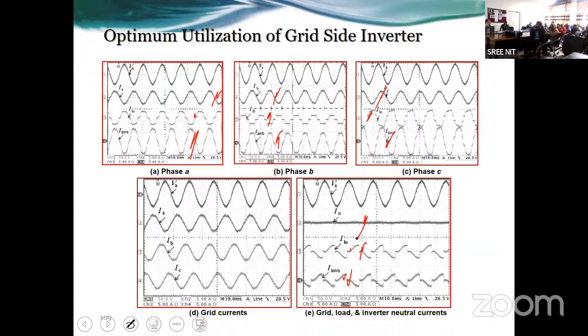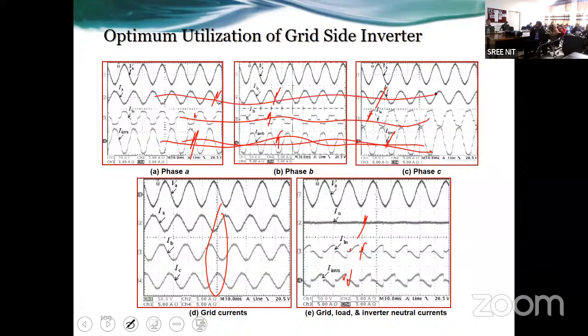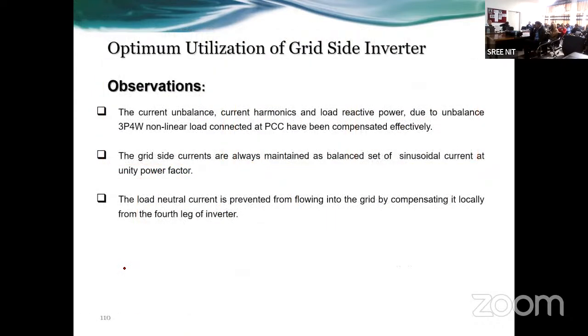So grid side neutral current is 0 because the unbalanced part I am supplying from the inverter itself. So the load unbalanced part I am supplying from the inverter. So that's why these are the perfectly balanced currents. These are the unbalanced part which I am supplying. This is the unbalanced load, unbalanced inverter injection, but these are the balanced grid side currents. Are you getting it? And this is evident from here. Inverter is giving just a complement of the load. So this is becoming 0. So this is what we have achieved experimentally at that time in my lab.